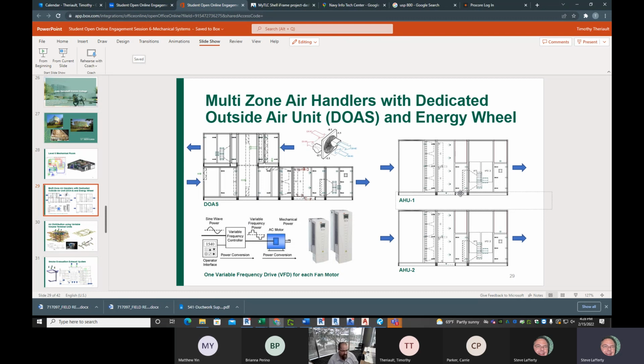If the building only needs half of its airflow, or if it needs 3/4 of its airflow, that fan will basically do that. And it does that by sensing through the building automation system, and has a couple of variable frequency drives, one attached to each fan. So each of these fans will have that to be able to control and modulate on a multi-zone variable system. The variable frequency drive takes power from the power source, and it modulates the hertz on it to bring the fan rotation faster and slower. So it's basically taking the sine wave power, modulating it down to this AC motor.